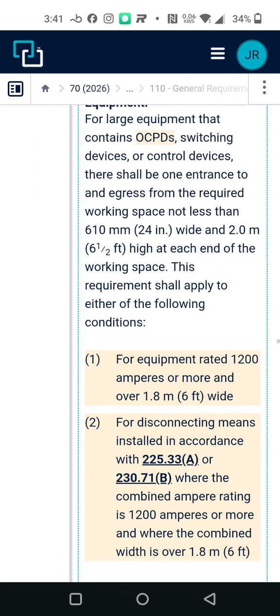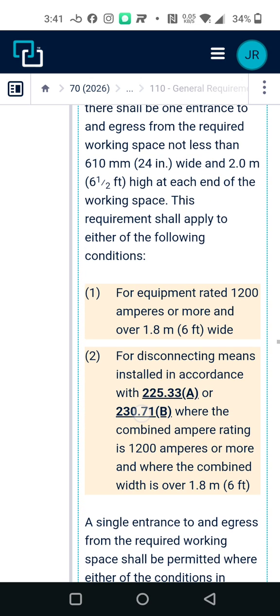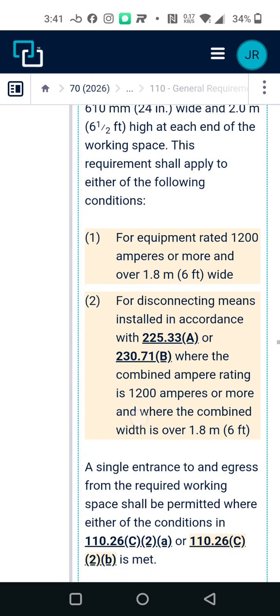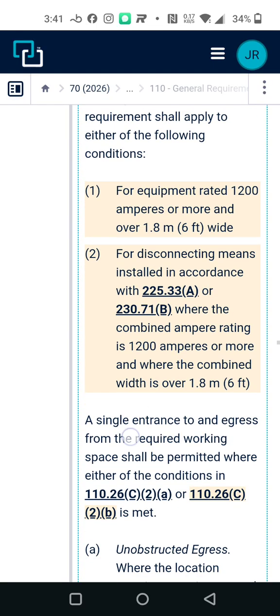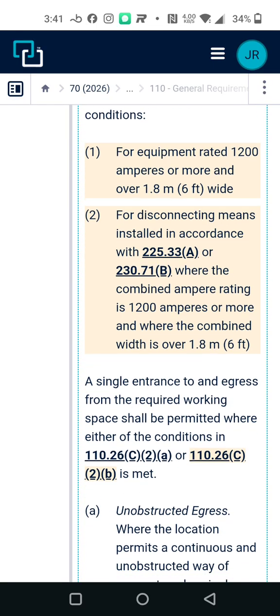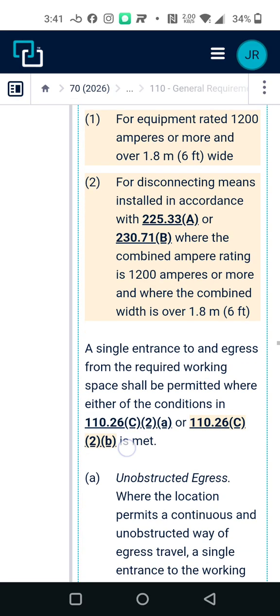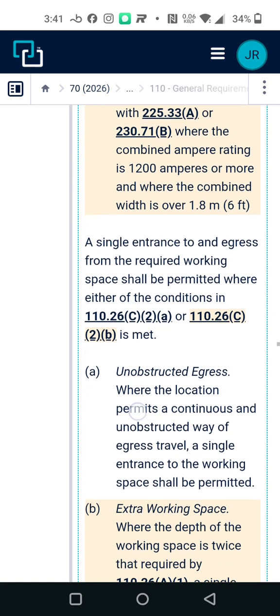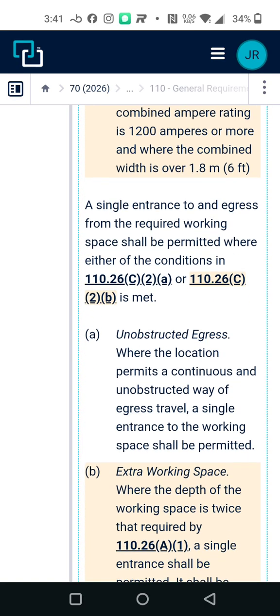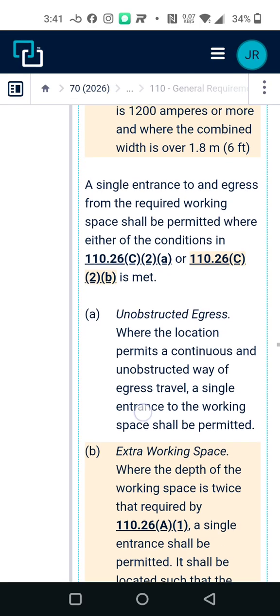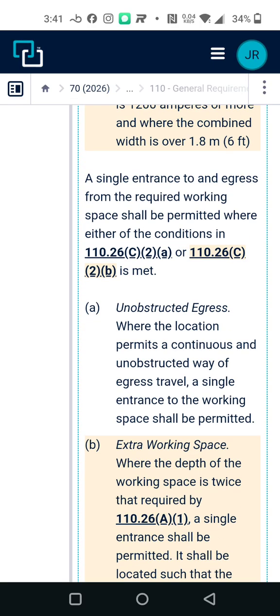This requirement should apply to either of the following conditions: for equipment rated 1200 amps or more and over 1.8 meters wide, or for disconnecting means installed in accordance with 225.33 or 230.71(B), where the combined ampere rating is 1200 amps or more and the combined width is over 1.8 meters. A single entrance to and egress from the required working space should be permitted where either condition in 110.26(C)(2)(a) or 110.26(C)(2)(b) is met.